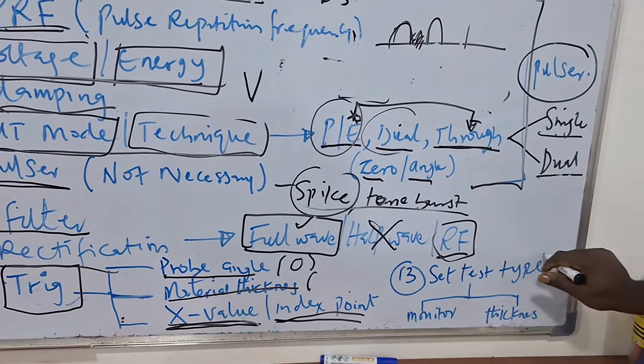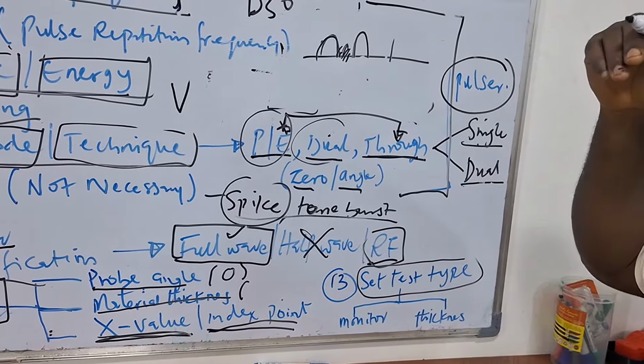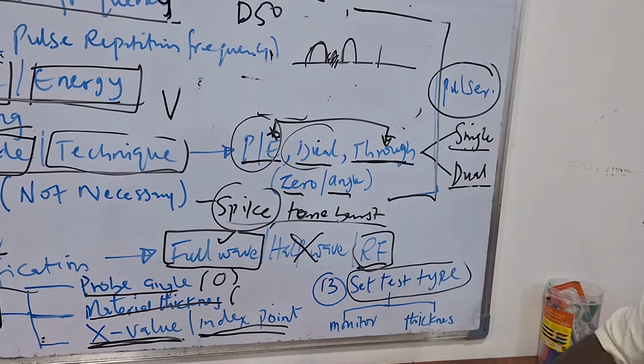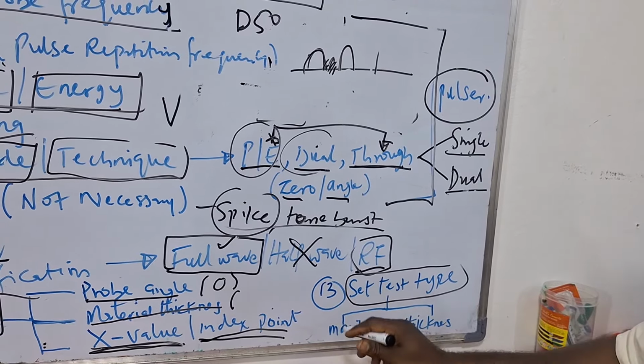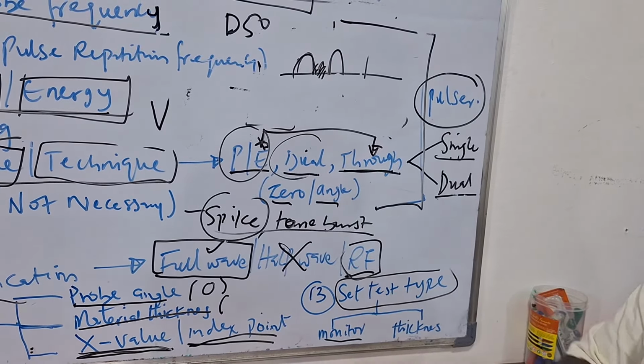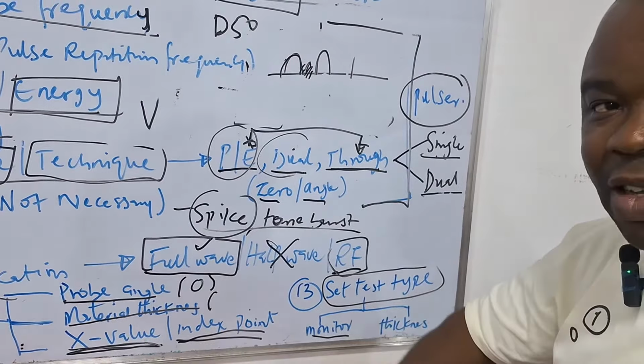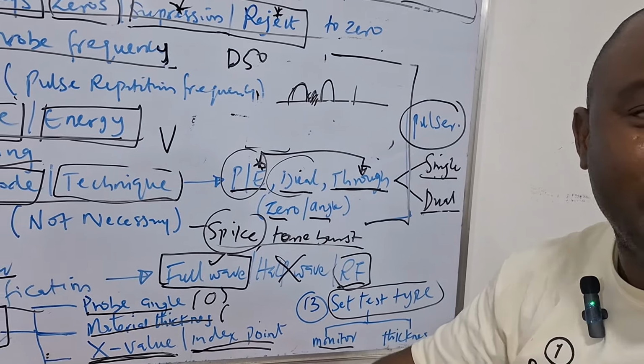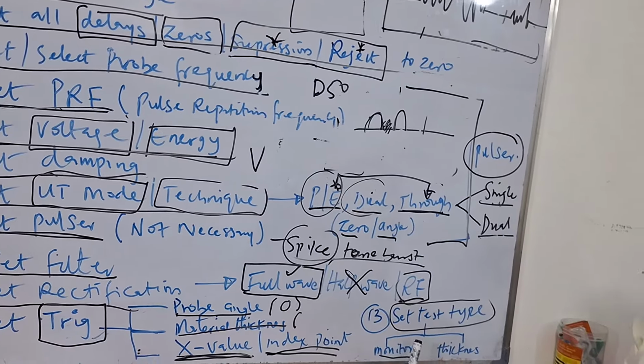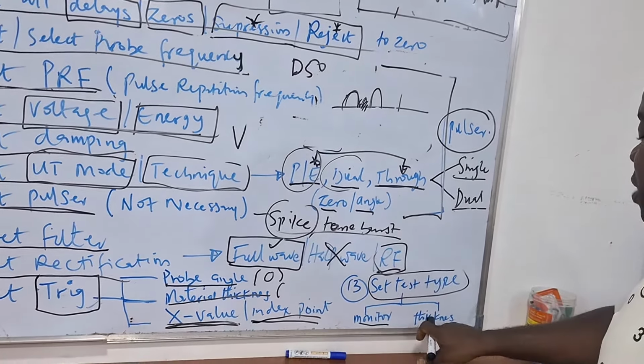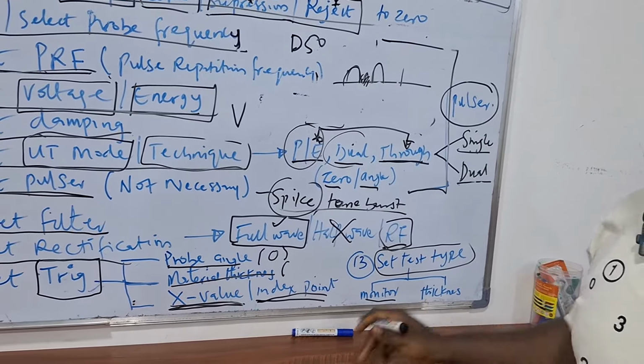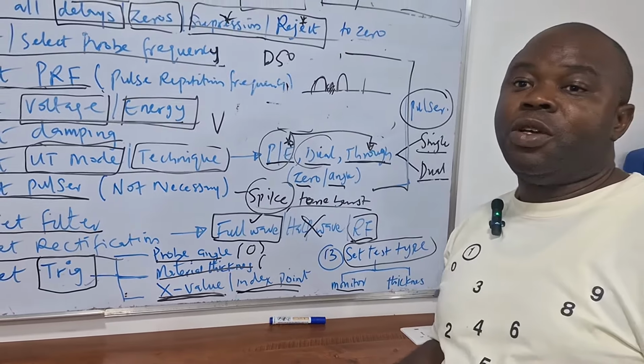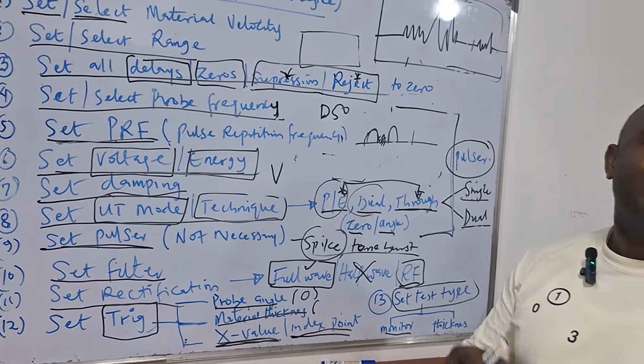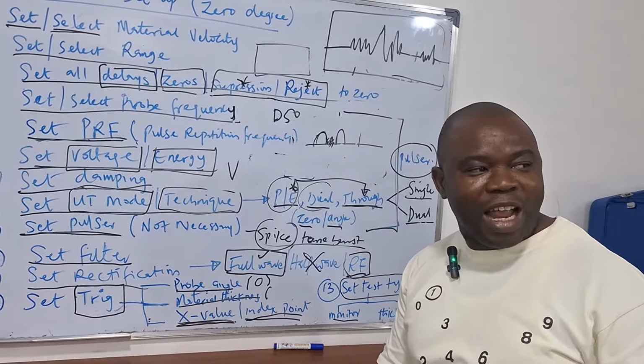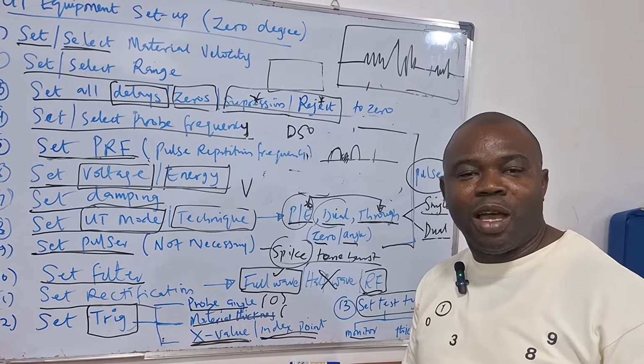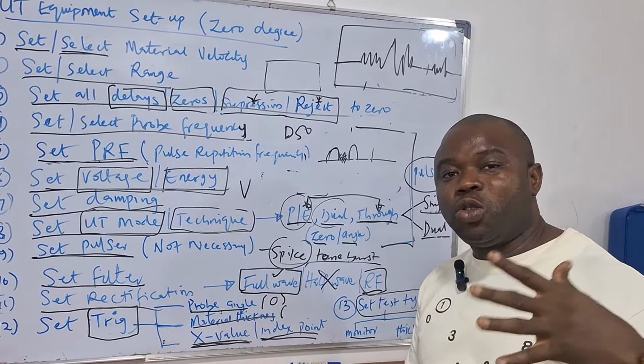The last thing you'll do is set your test type. This is very important, especially with units like Sonatest. Monitor mode just uses your probe to scan the surface and see variations in how the echo comes out - you may not get any reading. But if you're doing thickness measurement, please choose thickness measurement. There are other options with Sonatest: edge to edge, gate to gate, flank to flank, echo to echo - it depends on what you're doing.